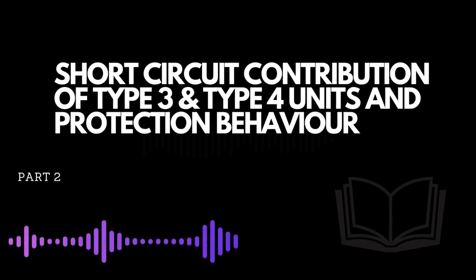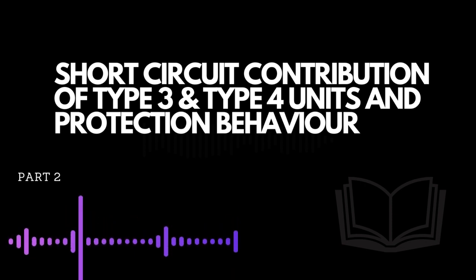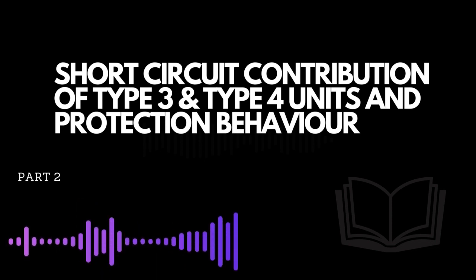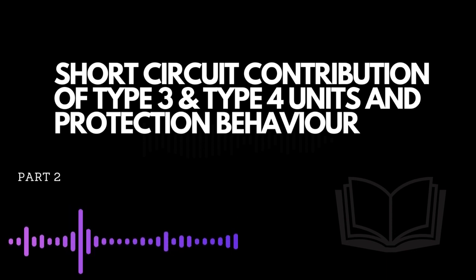Differential protection. This function is commonly used as main protection function to detect short circuits in line due to its high reliability. A communication channel is needed in order to exchange current measurements between both ends.